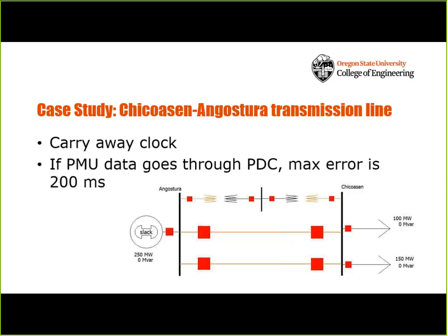We found a case where someone had actually tried this, and within about 4 minutes they were able to cause a 10-degree difference in the power system. That's from the start of the attack to the end, so it's not all that difficult. The 200 milliseconds here is actually the phasor data concentrator limit. If the PMU is behind by more than 200 milliseconds, including all delays through the entire system, then it's just going to ignore that data altogether.